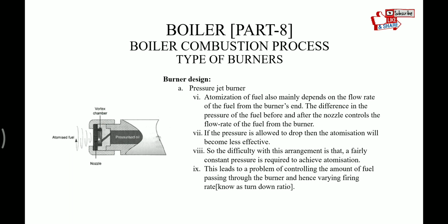Atomization of the fuel also mainly depends upon the flow rate of the fuel from the burner's end. The difference in the pressure of the fuel before and after the nozzle controls the flow rate of the fuel from the burner. If the pressure is allowed to drop, then the atomization will become less effective. So, the difficulty with this arrangement is that a fairly constant pressure is required to achieve atomization.